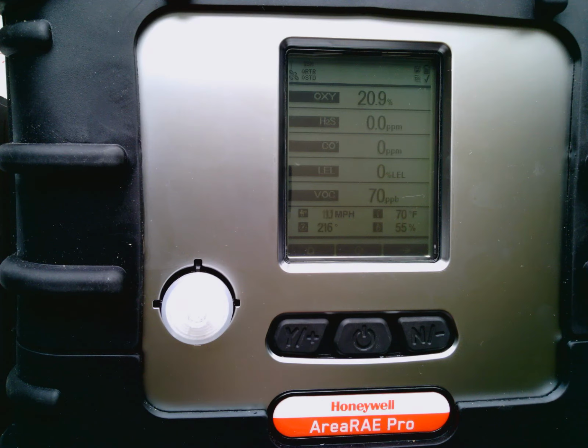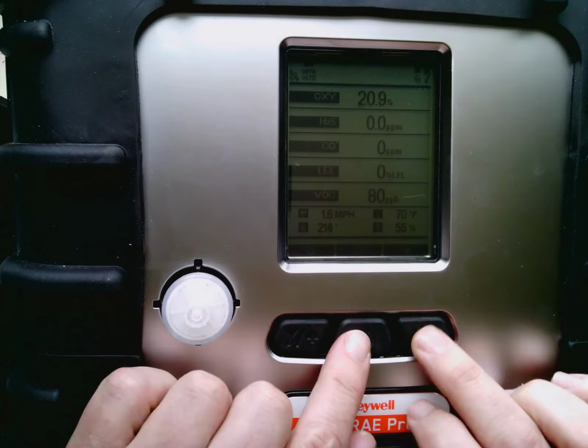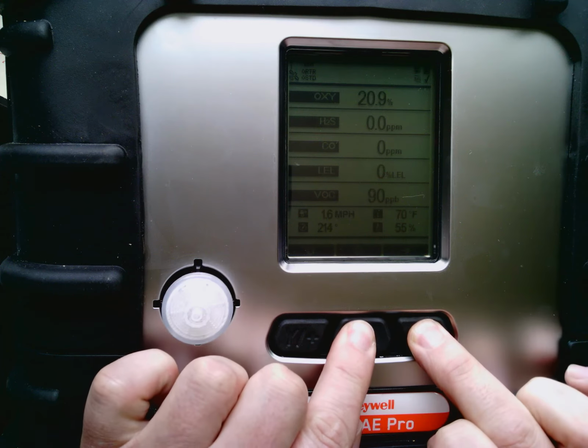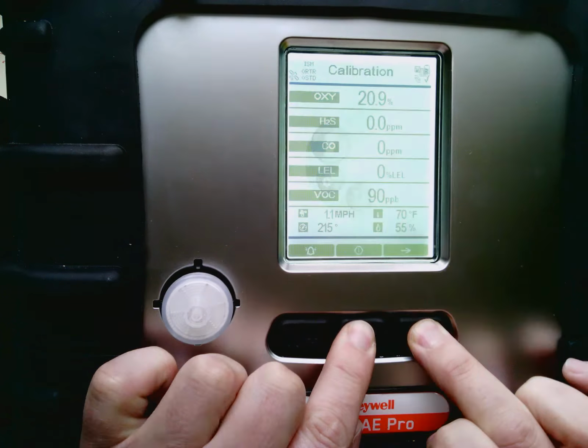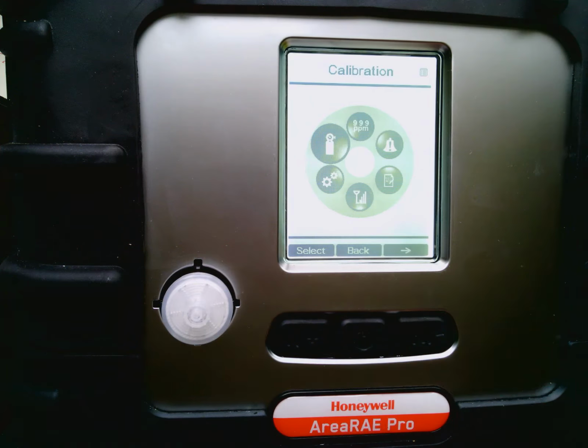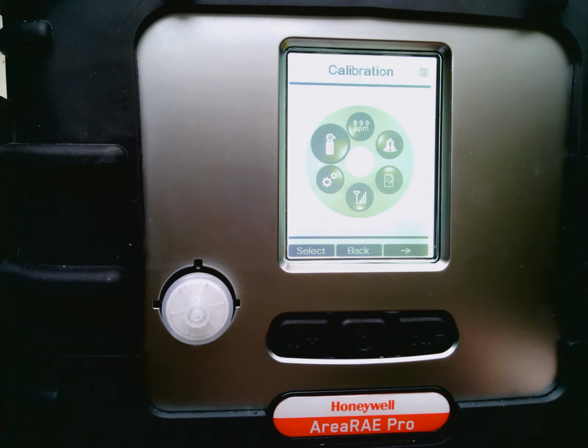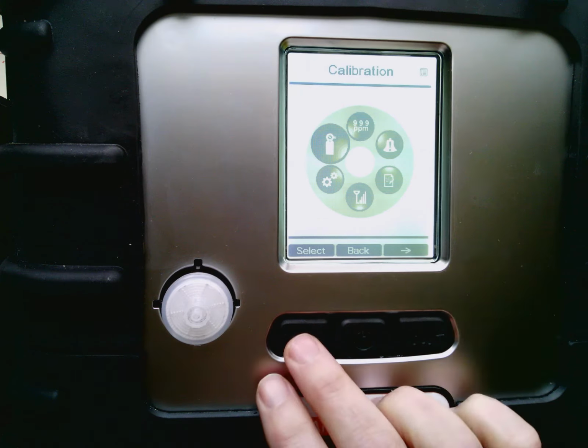Now we're going to perform a full calibration on an AreaRAE Pro. To do so, we're simply going to press the N and mode button. Now, if you didn't previously do a fresh air calibration or enter the password, this is where it would prompt you for it. The standard password from RAE on these units is 0000. Once you enter that, you'll get into this menu-driven process here.